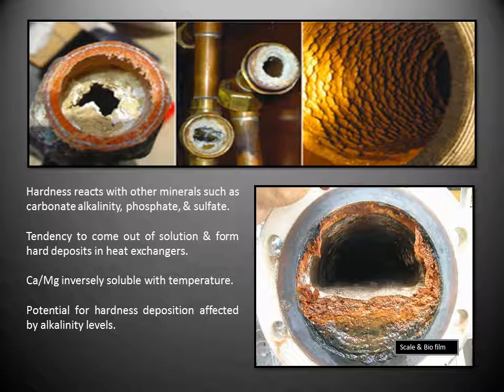Microorganisms present in the biofilm accelerate oxygen uptake. This can cause an oxygen deficiency in the system. Some microorganisms switch to fermentative metabolisms and produce a number of organic acids which cause a decrease in pH, resulting in anaerobic bacteria forming sulfide byproducts, which are in fact corrosive.